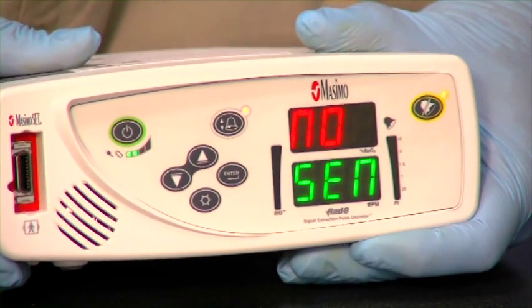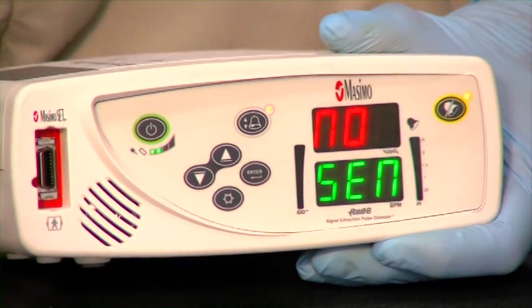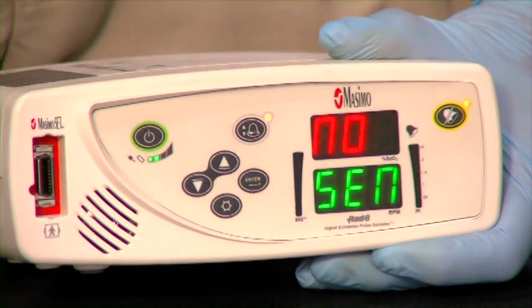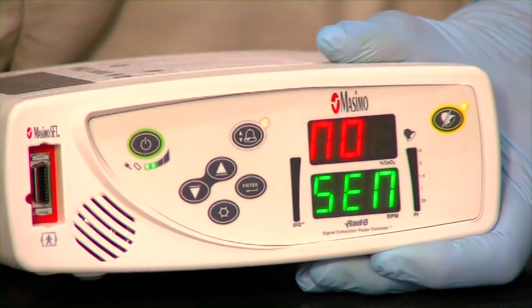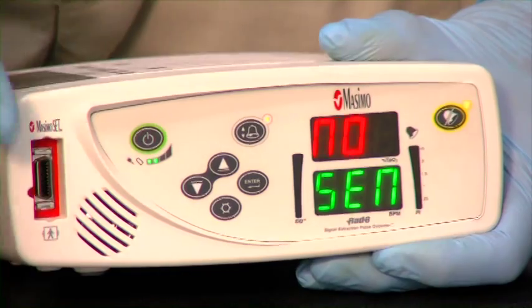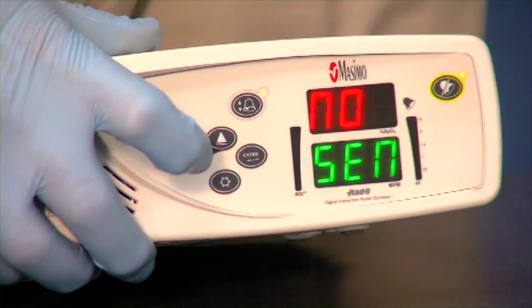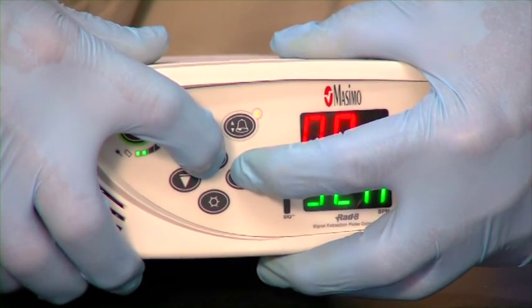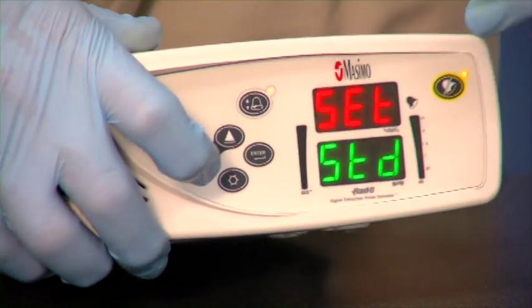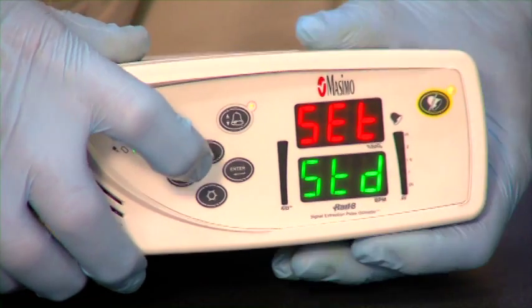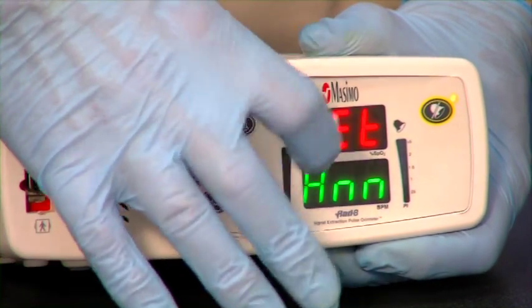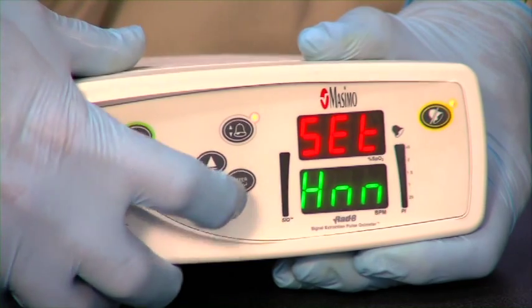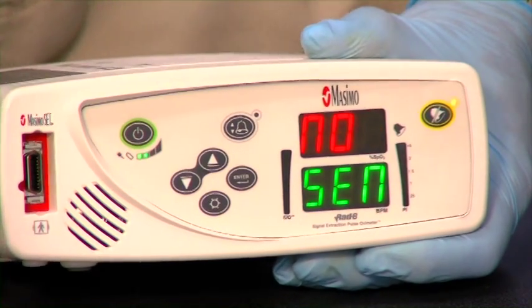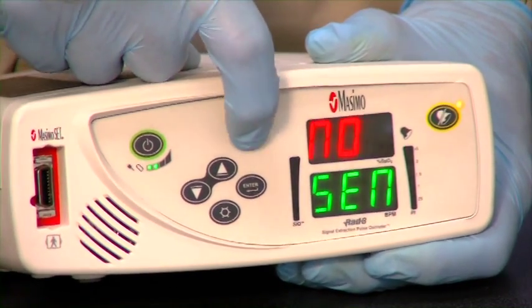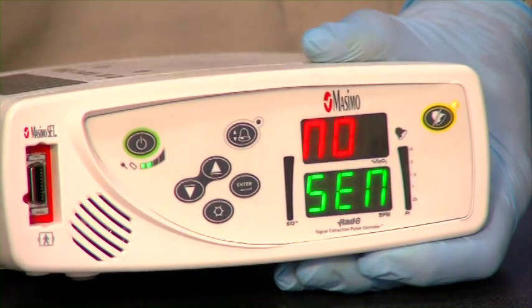Okay. So now before we take it out and put it on the patient, we want to lock that machine in so that nobody can adjust the parameters that we've set. And we do that by getting back into the selection mode, pressing the up arrow and the enter button until it reads set in the upper window, and we want to get back into that HNN mode, which is the home mode. We hit our enter, that locks our settings in. Now no one can get in and adjust those parameters.